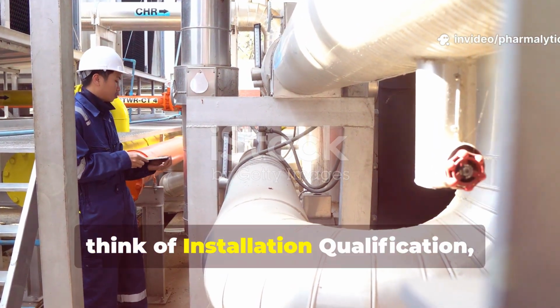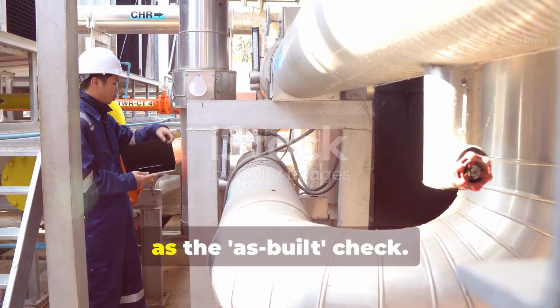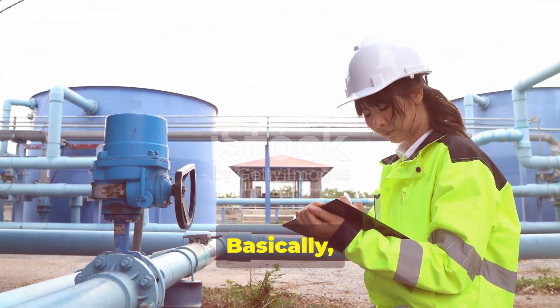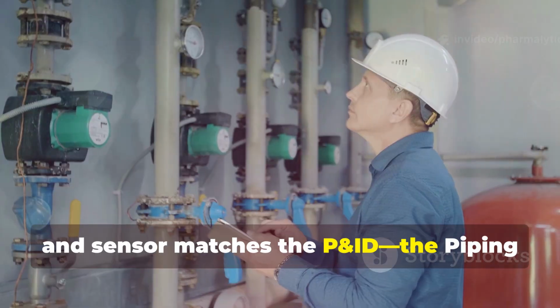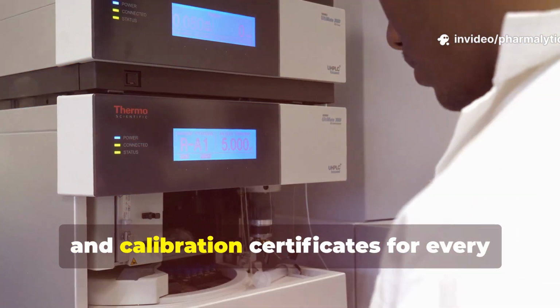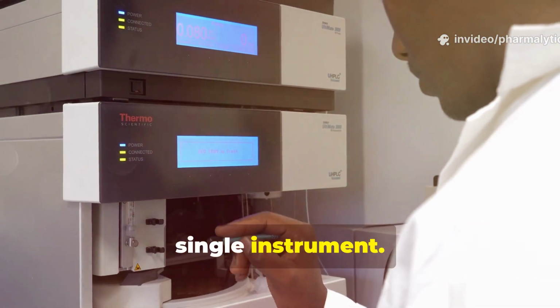So, think of installation qualification, or IQ, as the as-built check. Basically, you're verifying that every pump, valve, and sensor matches the P&ID, the piping and instrumentation diagram. You need traceability for every weld and calibration certificates for every single instrument. No certificate? Well, no compliance.